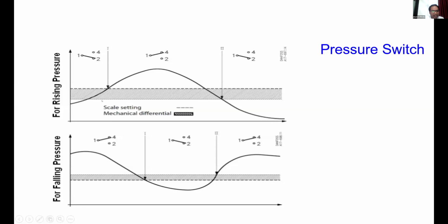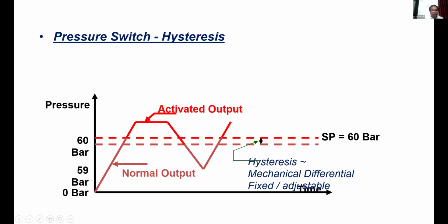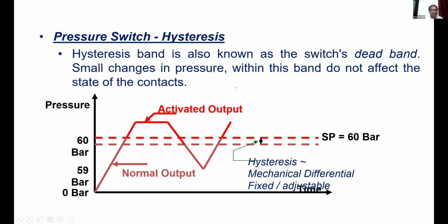Now see here, with the dotted line I have shown one band, and that band is called the hysteresis band, guys. On the y-axis I have taken the pressure, and with the help of this dotted line I have shown the hysteresis band. So what exactly is meant by the hysteresis band? For example, if you set 60 bar pressure, when the pressure reaches 59 or 59.5, the contacts of that sensor, or the relay if you connected one, get chattered. It means you will see continuous on and off, and it will hamper your overall system.